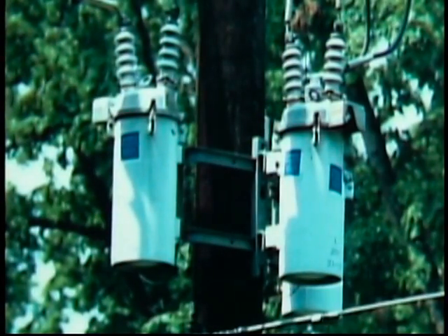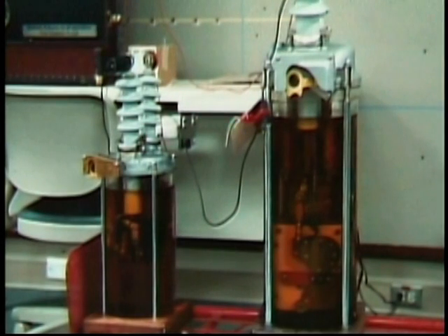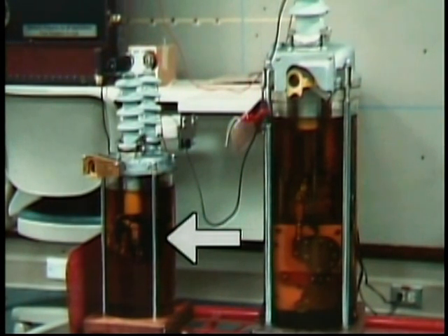Another protective device, called a sectionalizer, is a switch that opens a faulted circuit after the circuit has been de-energized by a recloser or by another protective device, such as a substation circuit breaker. Sectionalizers look very similar to reclosers. The tank of a single-phase sectionalizer may be smaller than the tank of a single-phase recloser because most sectionalizers aren't designed to interrupt fault current.